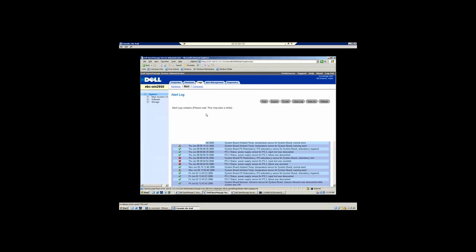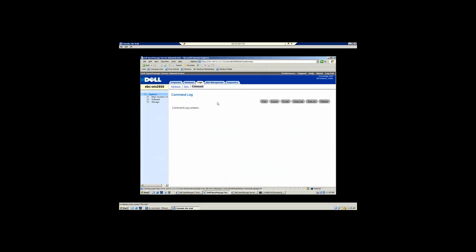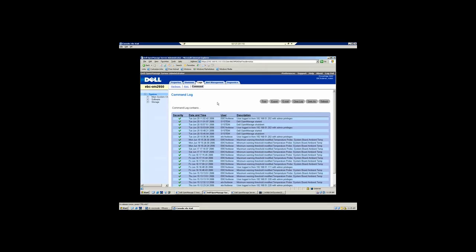The alerts gives you the SNMP traps that have been created as a result of changes. And then the command is probably one of the nicest features in Server Administrator in that not only does it tell you who logged in, but it tells you from where they logged in and what privileges did they have as well as the date and the time. So a good amount of detail there.